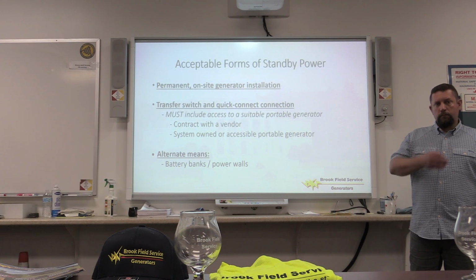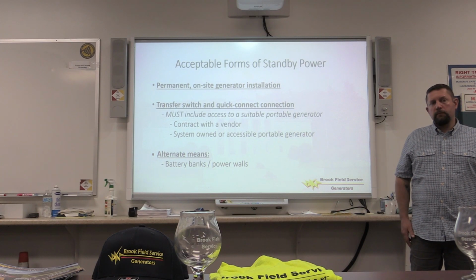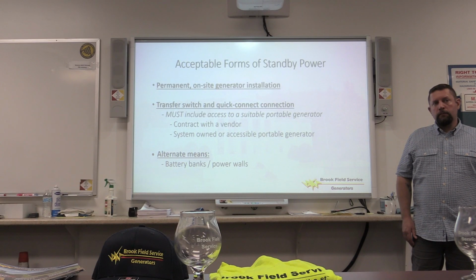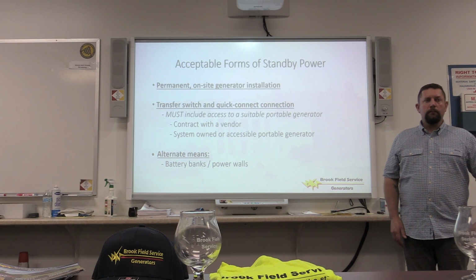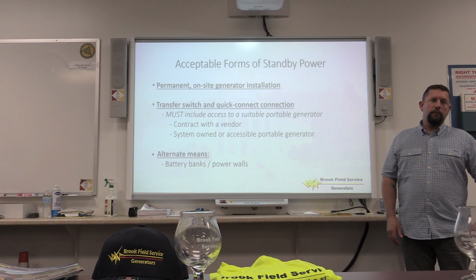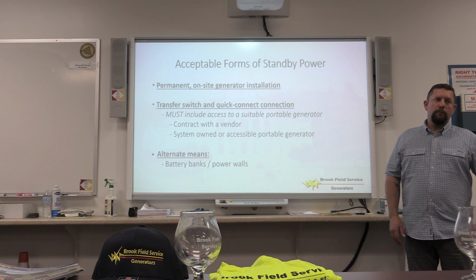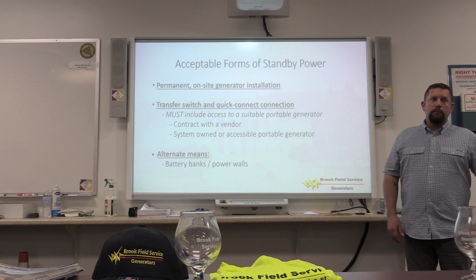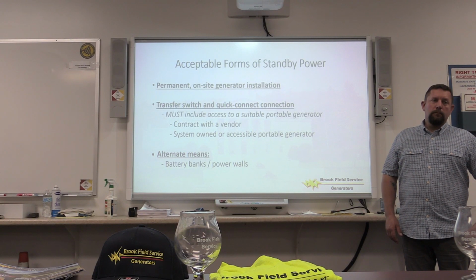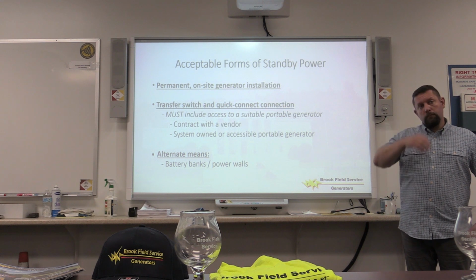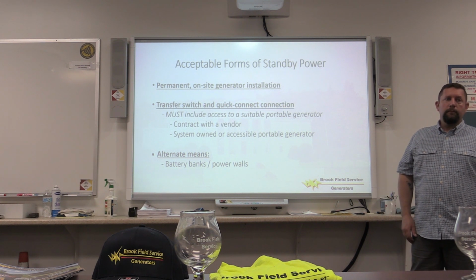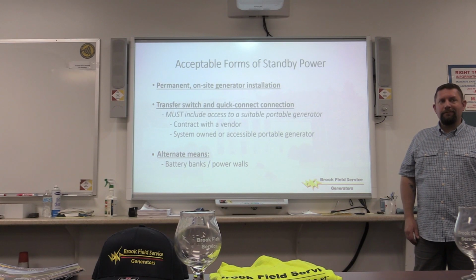We did one for a nursing home in downtown Montpelier, 300 kW. Basically, what you're doing is converting a diesel engine to work on propane. And so the cost of those generators is probably 3 times their diesel counterpart. And they require a lot of gas. A generator like that requires 4 1,000-gallon tanks to run. So it could be a bit of a challenge sometimes to just store that much gas. But most freshwater pumping stations, 100, 150 kW, will handle the loads that are there.